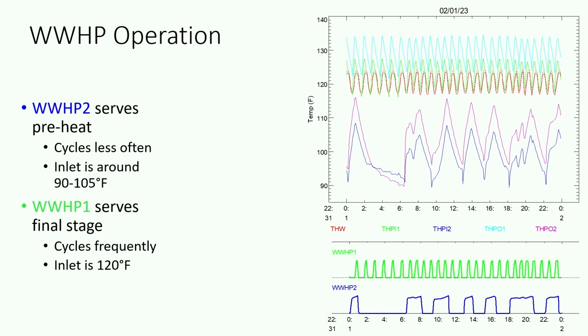So here's heat pump number 1 that had served the finished tank, and here's heat pump number 2. And so, of course, the one on the finished tank cycled more often. It was trying to keep the tank hot, and you can see that the final tank's heat pump inlet was typically 120, and then it would go out at 130 or 135. And then for the preheat tank, it was typically about 90. So that one had higher efficiency, and it cycled less often.